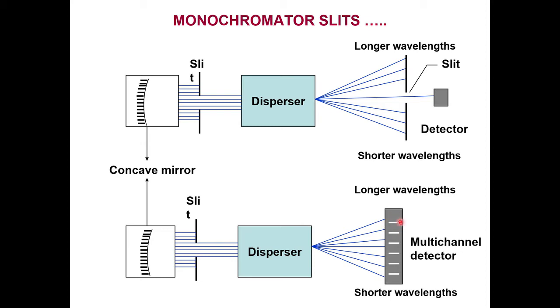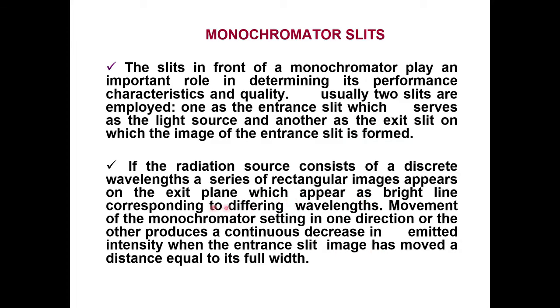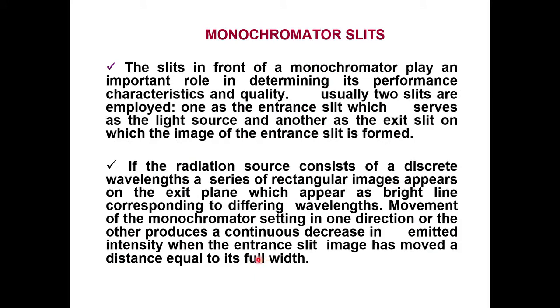A multi-channel detector allows picking up as many wavelengths simultaneously as needed. This is a typical arrangement in almost all spectrophotometers including atomic absorption. The slit in front of a monochromator plays a very important role in determining its performance characteristics and quality. Usually two slits are employed: an entrance slit and an exit slit. The entrance slit serves as the light source, and the exit slit shows the image of the entrance slit. Moving the monochromator setting produces a continuous increase or decrease of the wavelength.